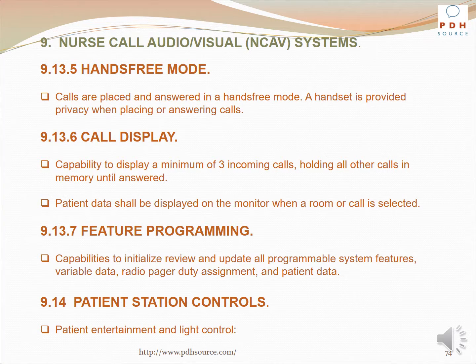In the hands-free mode, calls are placed and answered. A handset is provided for privacy when placing or answering calls. Capability to display a minimum of 3 incoming calls, holding all other calls in memory until answered, shall be provided. Patient data shall be displayed on the monitor when a room or call is selected. Capabilities to initialize, review, and update all programmable system features, variable data, radio pager duty assignment, and patient data shall be provided. Patient entertainment and light control shall be provided.